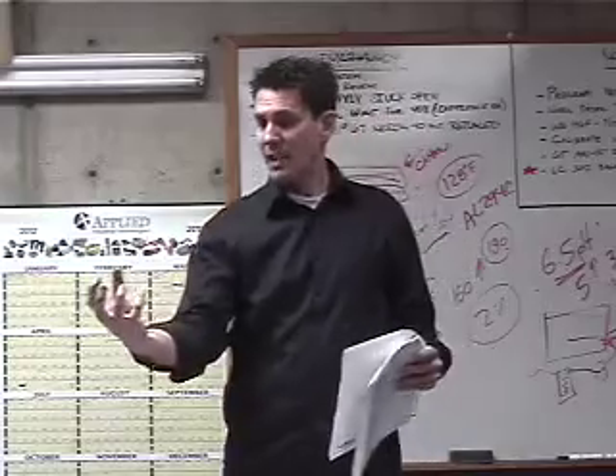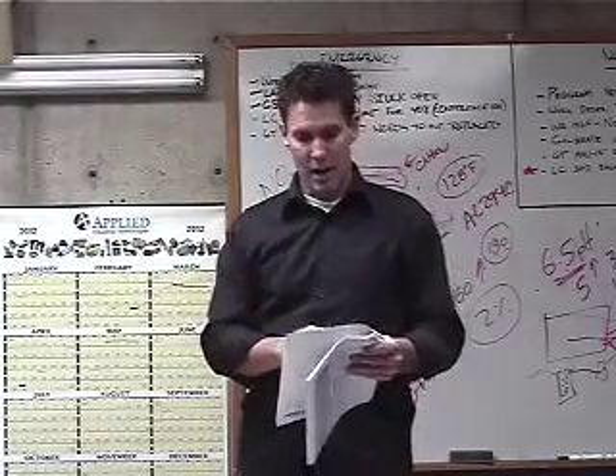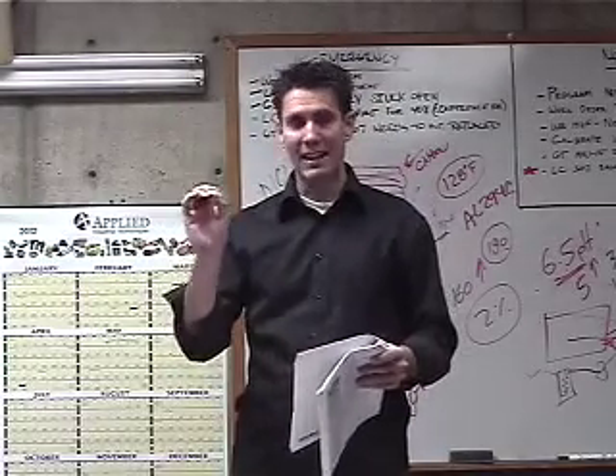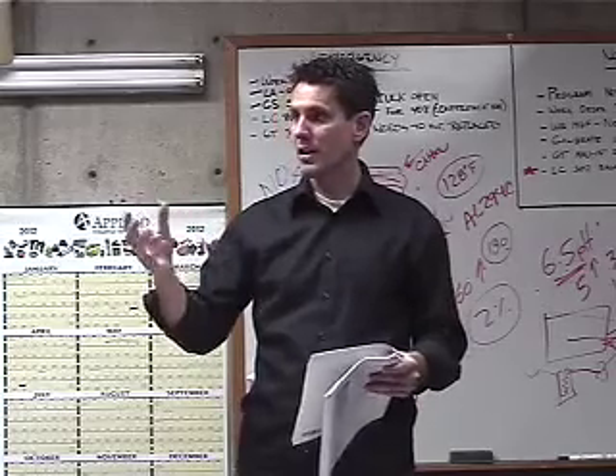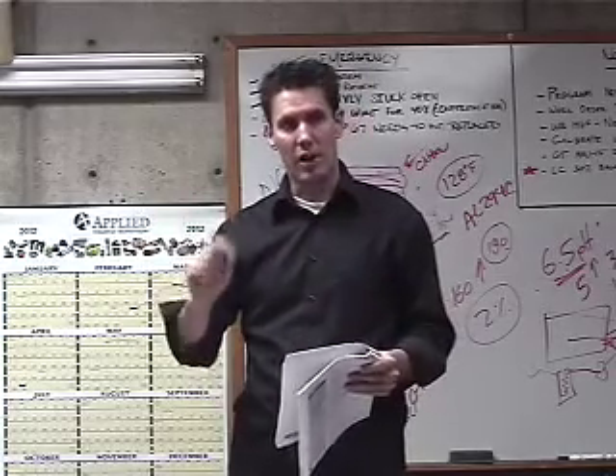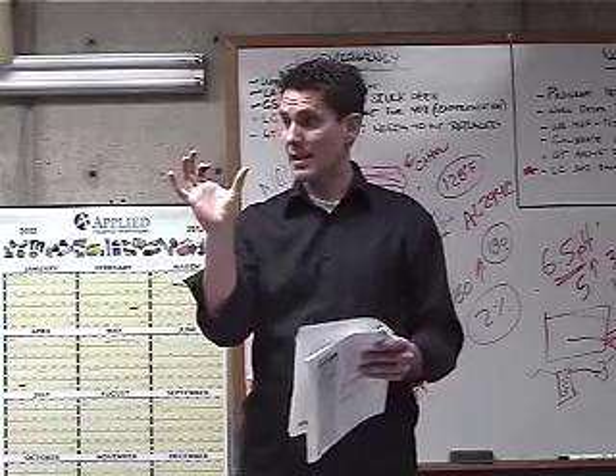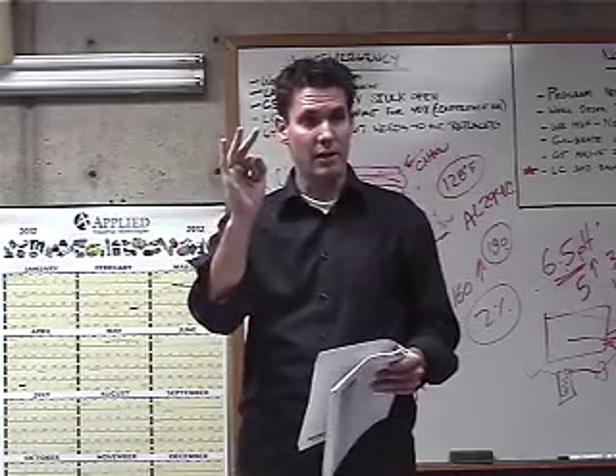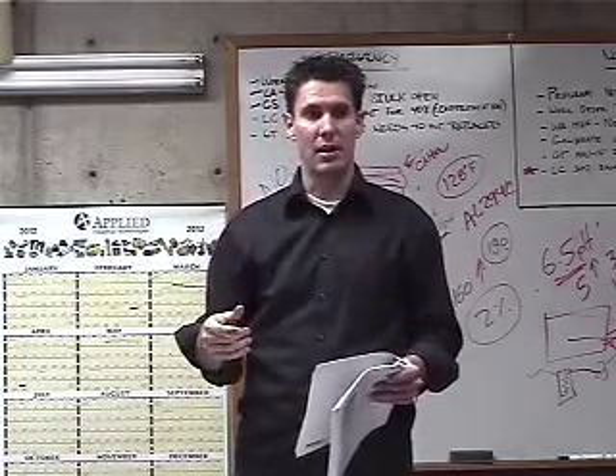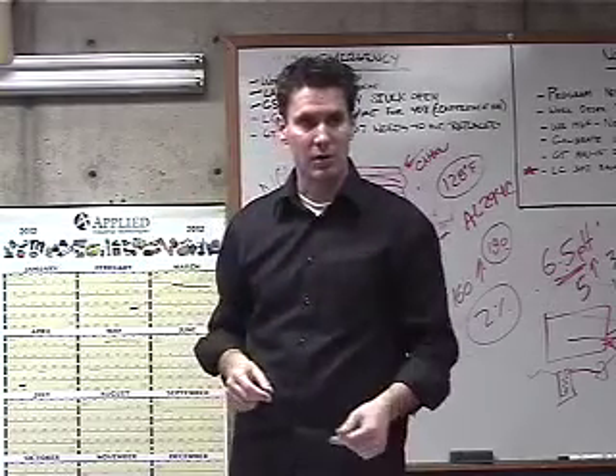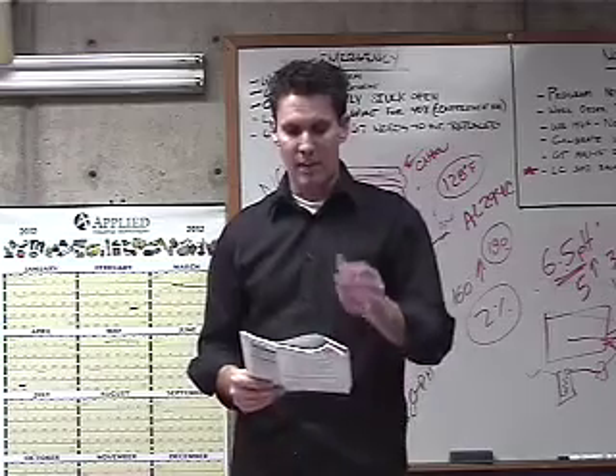My boiler has a call for heat, but my fan's not turning on. If your high temperature, your high limit controller is tripped, then that's locking everything out. So you'll want to check that. Your high temperature limit control has a little red button on it. Push the little red button and see if that trips it. Make sure that the temperature on the boiler is not exceeding what that high temperature limit is set to. You might need to make some adjustments.